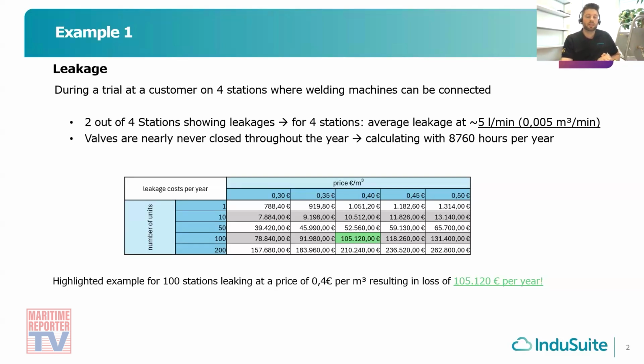In this first example, we initiated a trial together with the customer on 4 different machines. Right away, when we installed our system on 2 of those machines, we detected a leakage—a constant flow of gas out into the atmosphere. Basically, you buy the gas, it leaks somewhere, and you lose it out into the atmosphere. Calculating the average of those 2 machines of the 4 we have, we ended up with a value of 5 liters per minute of leakage.